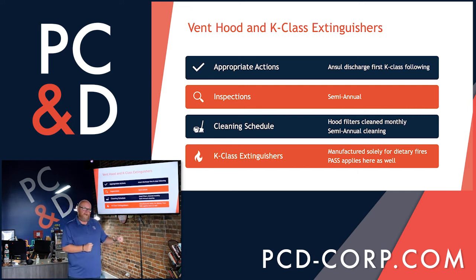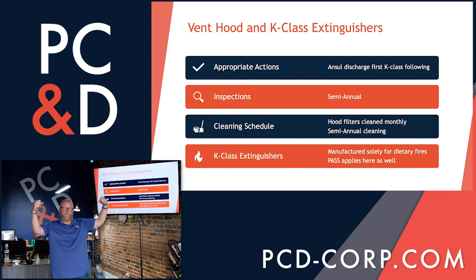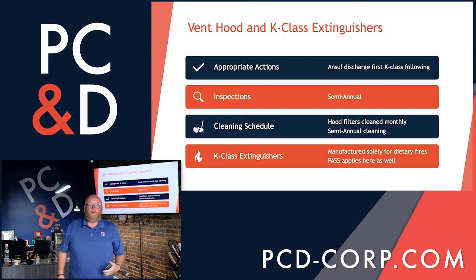So when you go pull that device, if you look closely, inside of that pull station is a cable. That cable goes up, and for lack of a better term, it's like a fancy mouse trap. You pull that cable, it runs around, and it does several things. One, it shuts off all of the power to your cook line, whether that be electricity or gas. So when you pull that system, it shuts your cook line down. So the source of the flames or the source of the heat is shut off instantly. While it also shuts down the cook line, it also engages the suppression system, and here comes your wet chemical to put the fire out. At the same time, your hood system is running and it's pulling all the smoke out. All of that is tied together.